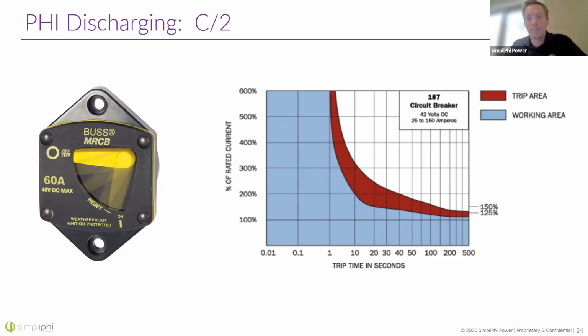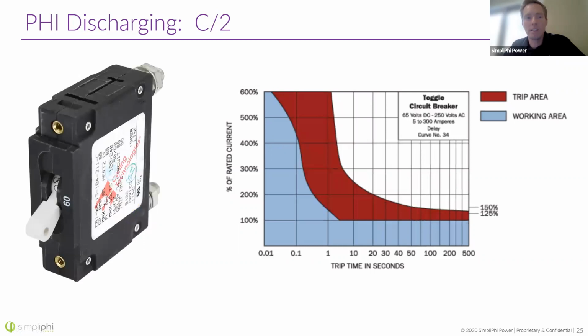But look at the time on the horizontal axis. If I'm only about 10% above 60 amps, so suppose I'm approaching 67, 66 amps, it's going to take 500 or more seconds for this thing to trip, right? If I hit 125% of that load, 125% of 60 amps, that's 15 extra, that's 75 amps. It's still going to take 100 plus seconds to trip, over a minute. So some damage could happen if you're relying on breakers to protect your batteries. And even at 200% load, this breaker will pass 120 amps for 10 seconds before shutting off. Okay, so keep that in mind as you're sizing breakers, and each breaker is different.